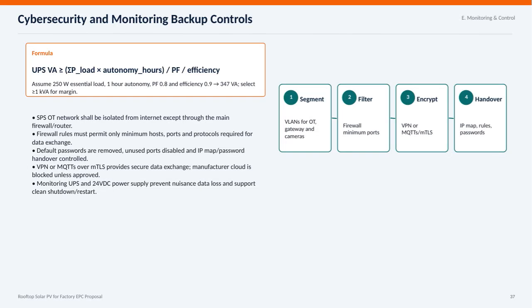Here we focus on cybersecurity and monitoring backup controls for rooftop solar PV in a factory EPC proposal. A critical formula for sizing the UPS is shown. UPS VA must be greater than or equal to the sum of the load power times autonomy hours, divided by the power factor and efficiency. For example, with a 250 watt essential load, 1 hour of autonomy, a power factor of 0.8, and efficiency of 0.9, we calculate about 347 VA, but select at least a 1 kVA UPS to provide a safe margin.